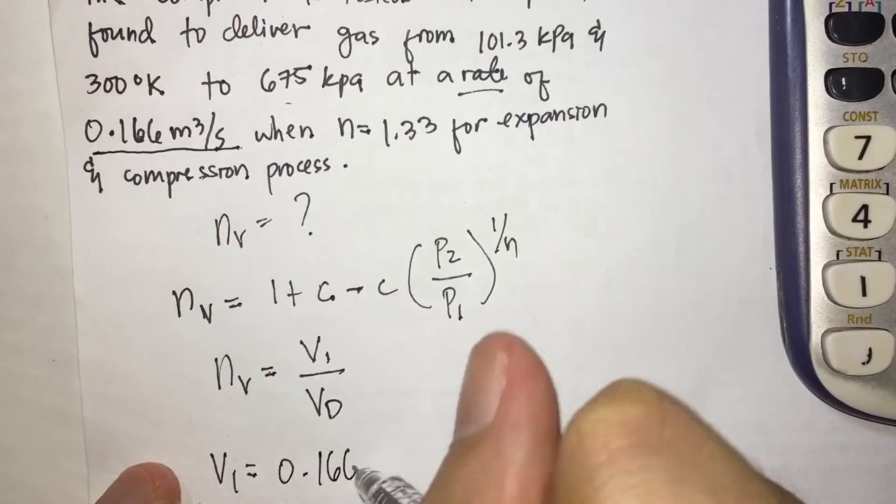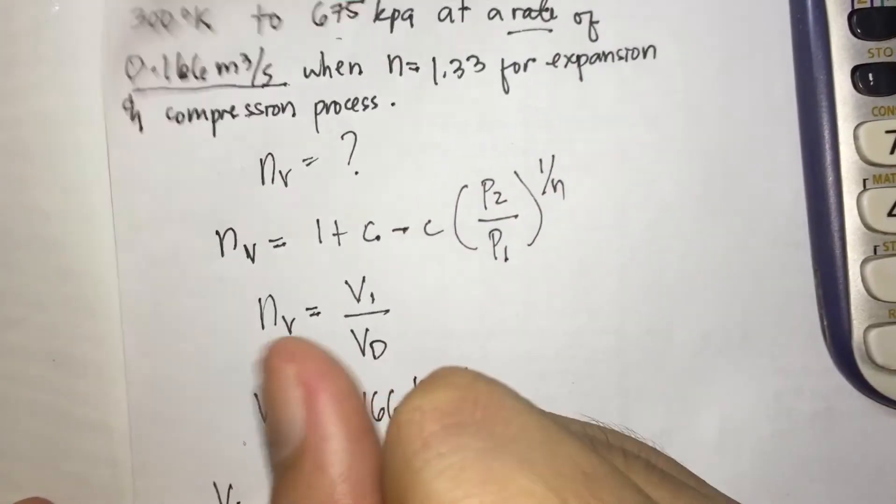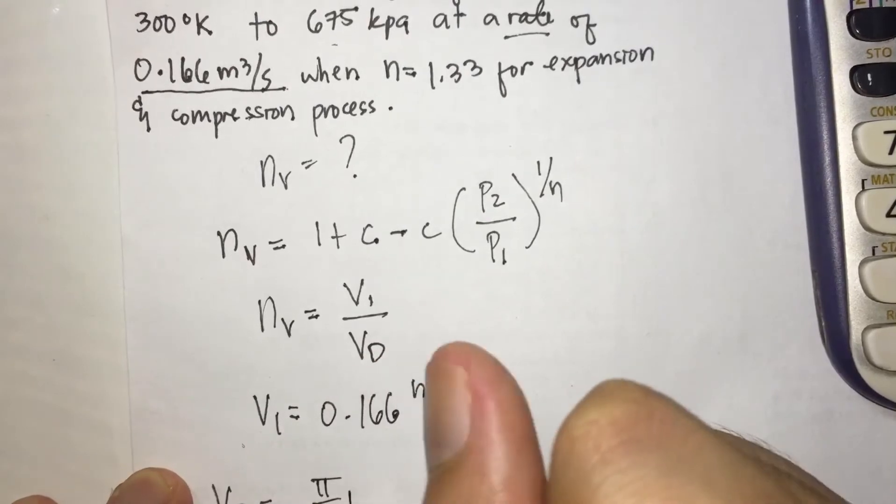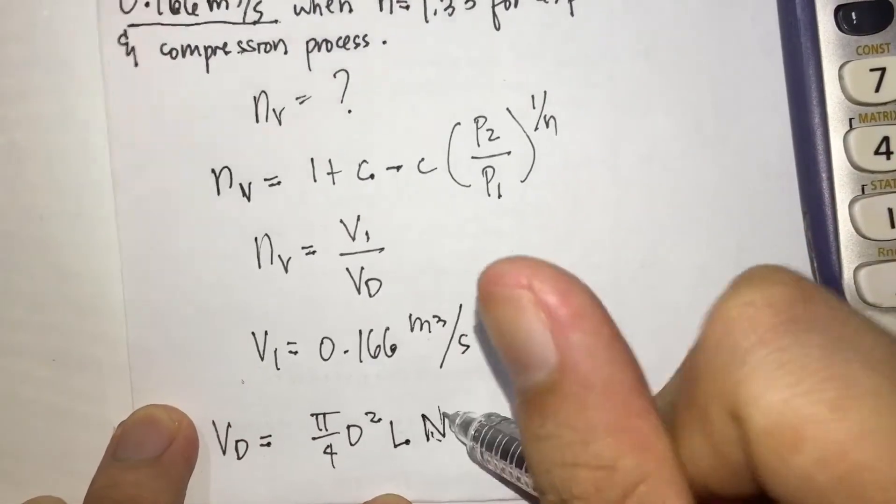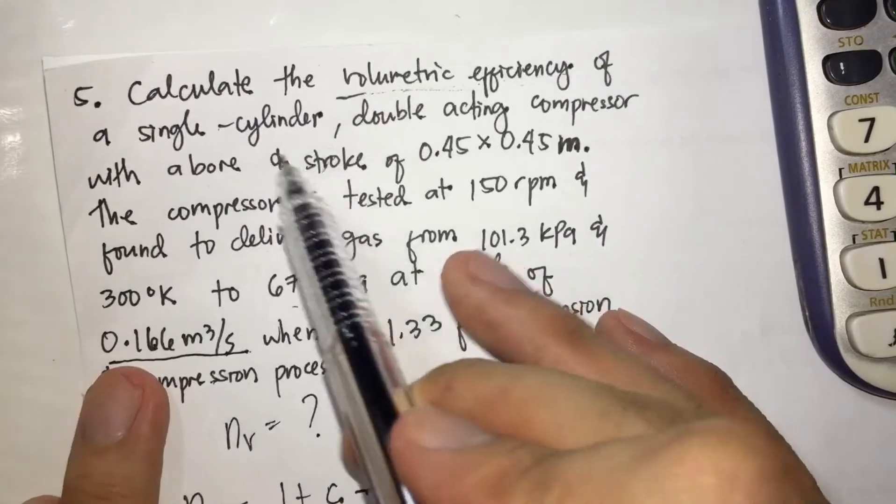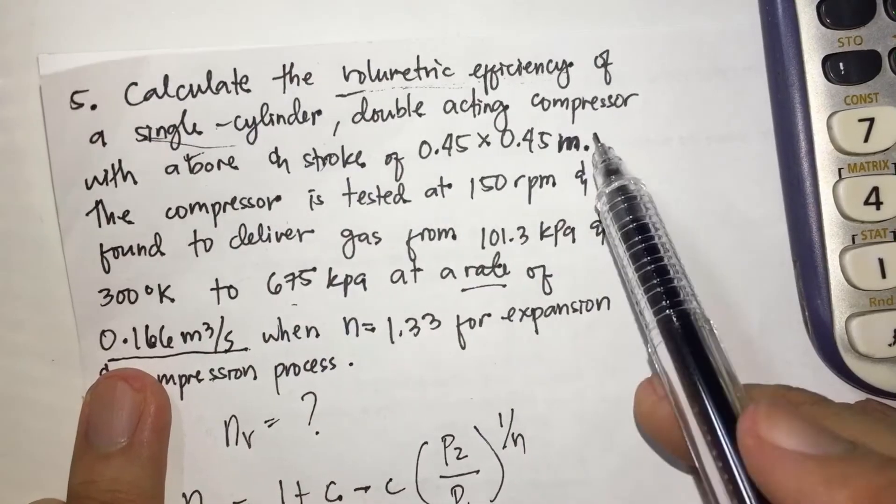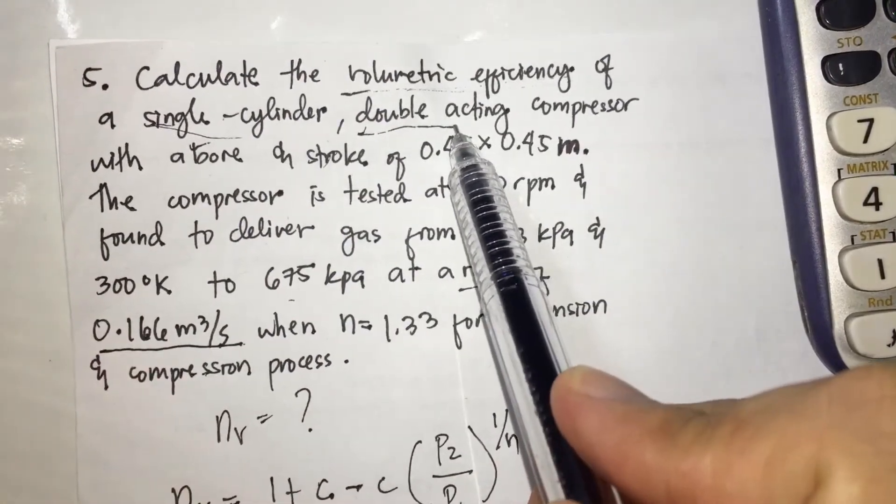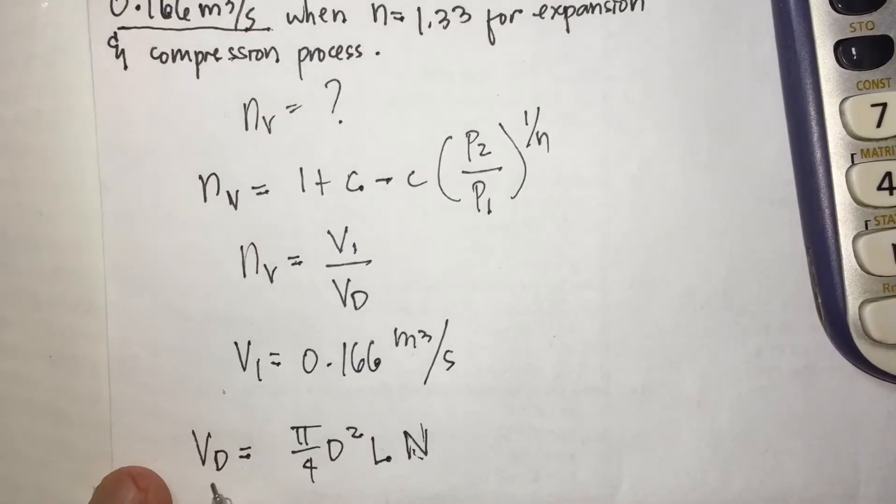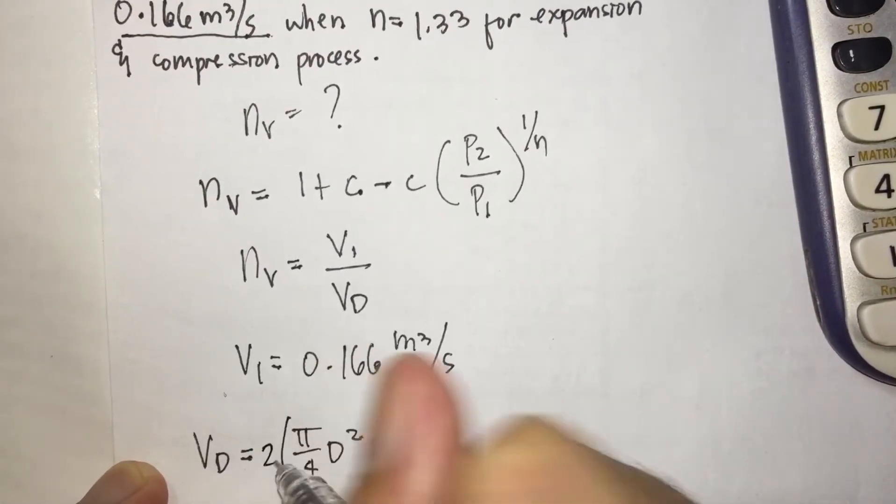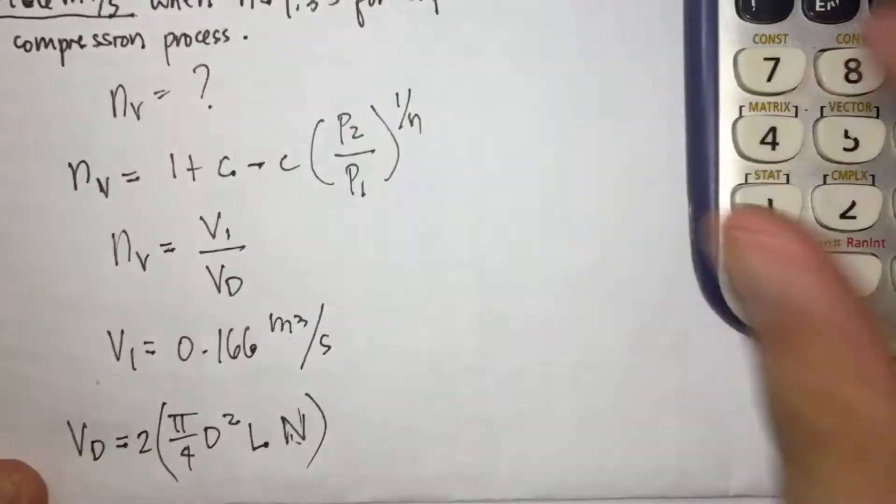And we'll find VD which is volumetric displacement, pi over 4, D squared times stroke times N. But you should look carefully at the problem because it says single cylinder double acting compressor. When there's double acting, the volume displacement should be times 2. That's where you'll make a mistake if you don't see the double acting, you won't multiply by 2.